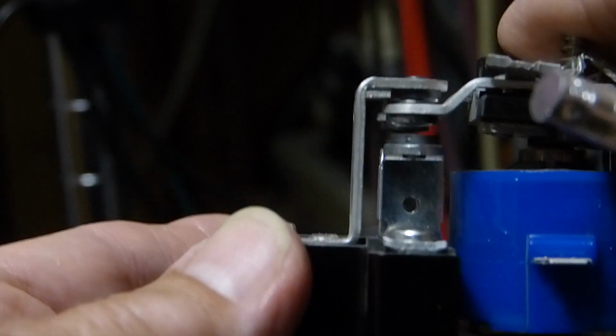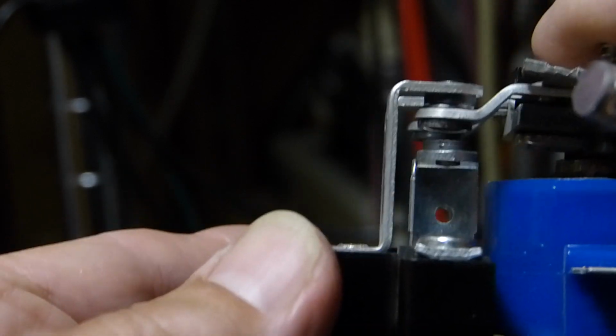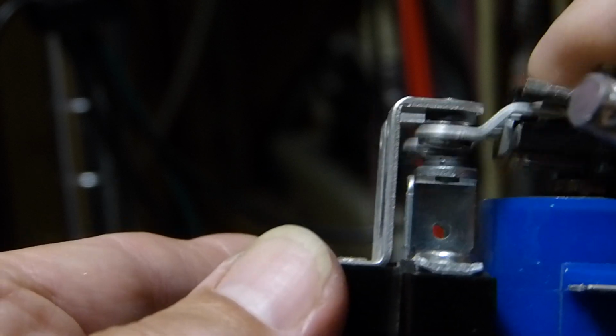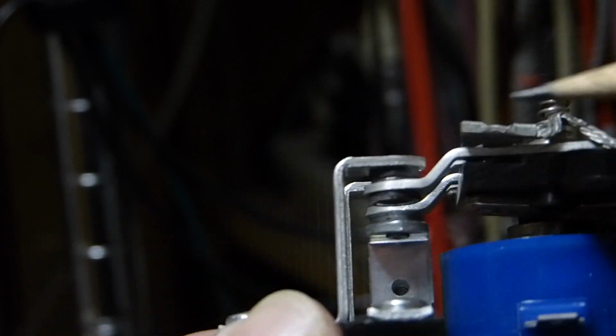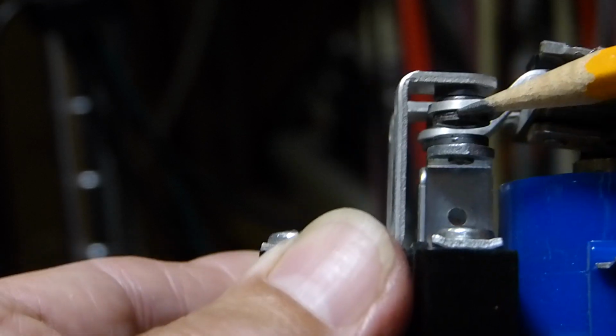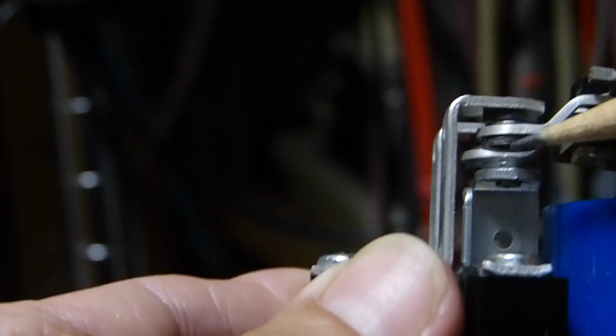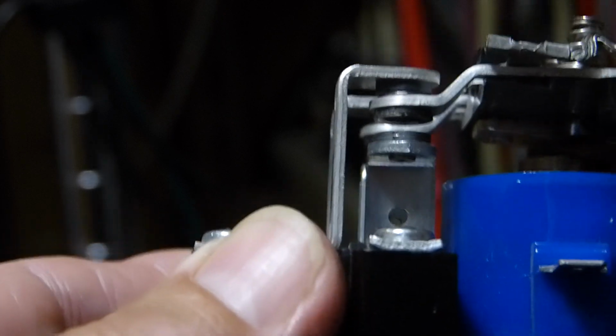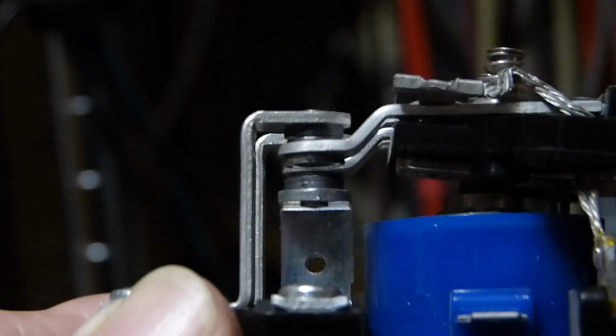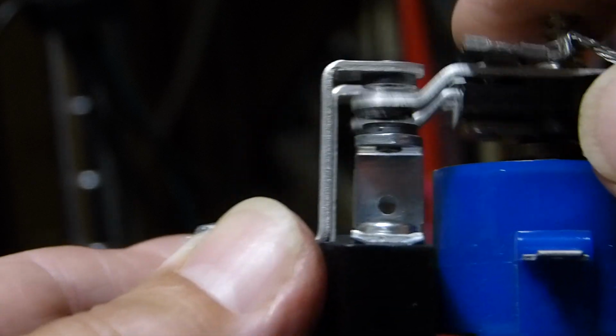You get an arc right there — a little blue arc, a little spark when you close it. Now, if these contacts don't come far enough apart, the arc is going to be sustained through there because it's got the air ionized. Now, these come apart far enough that they would probably extinguish the arc.